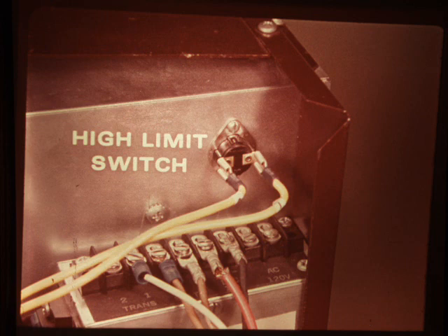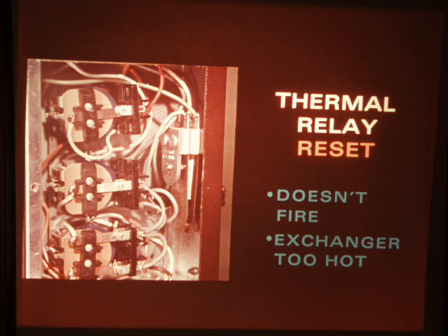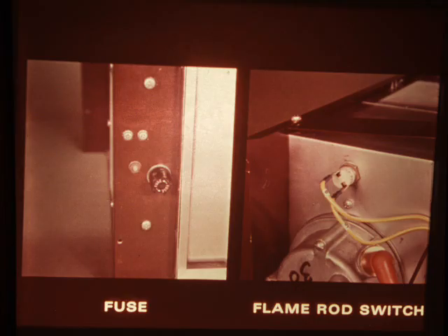It will open the solenoid valve circuit if the heat exchanger gets too hot and close it again when it cools. The thermal relay trips a reset and shuts the furnace down if the furnace doesn't fire for any reason, or if the high limit switch isn't working and the heat exchanger gets too hot. The electric control system also includes a fuse for overload protection, which is part of the control box, and a flame rod switch installed in the burner.